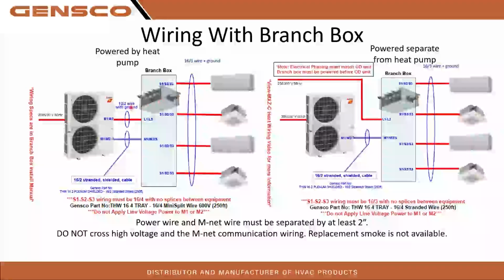If you're using that, what's recommended is a single branch box, or if you're planning to upgrade in the future to dual branch boxes, if you're doing a single branch box, 14/2 wire will be fine for your power. If you're planning to run multiple branch boxes, or have plans for expansion in the future, upsizing to a 12/2 would probably be a good idea. It's not going to hurt it. There's no communication happening on that B1, B2 to L1, L2 in your branch box. It is just power, just powering up your indoor equipment in that branch box. So you don't need to use the cable tray wire, anything like that. That can just be standard Romex.